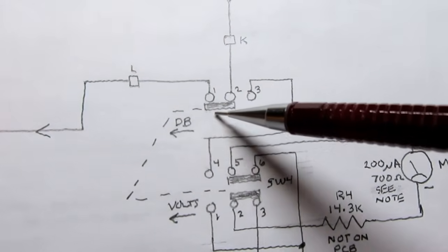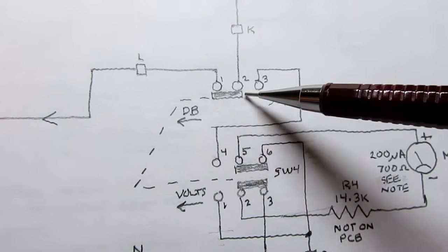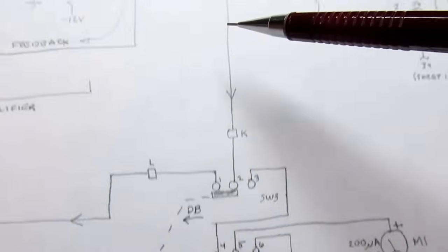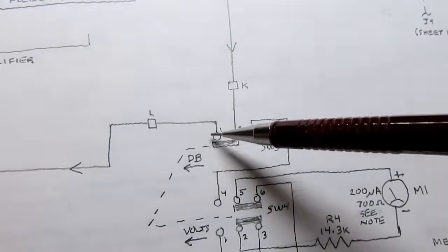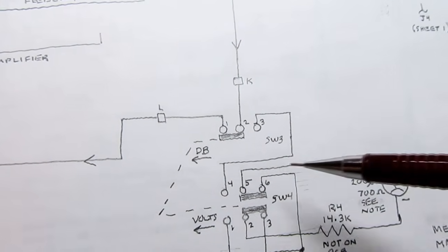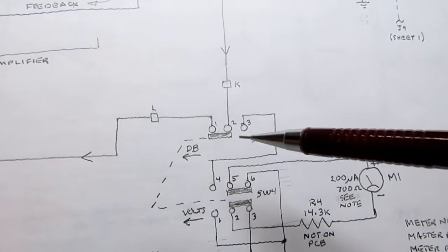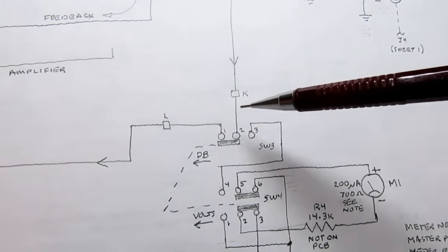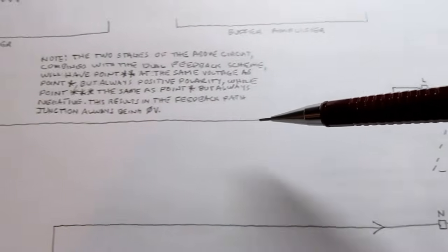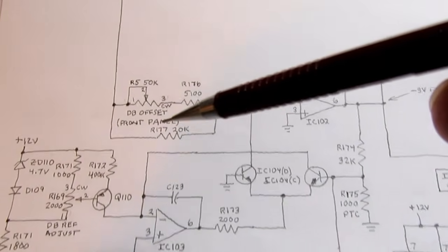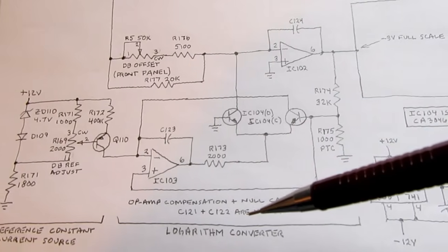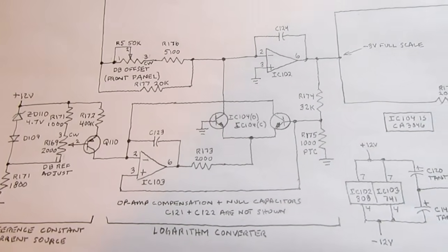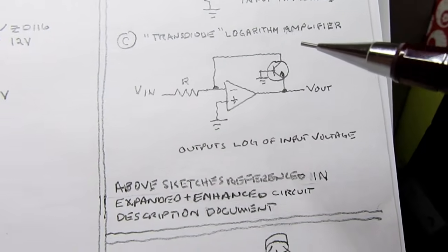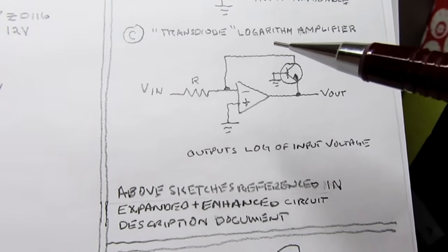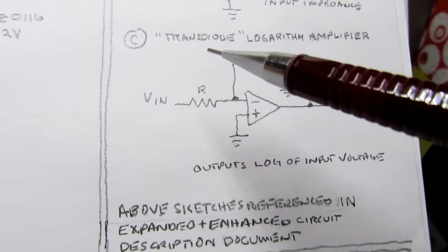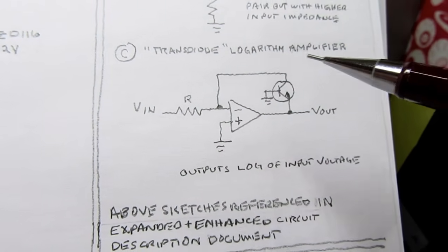So if we're in dB mode, now the switch is in the position shown here, and that 0 to 3 volt signal comes here and goes through this way, it can no longer go to the meter movement. The meter movement has been disconnected from this direct 0 to 3 volt signal. So the signal comes through here, and it comes around here, and it goes into the logarithmic converter. So I go back to my little sketch on sheet 3, and I showed what's called a transdiode logarithm amplifier.